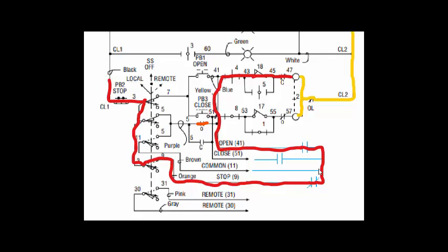that does is that brings voltage to this common wire to this contact on a selector switch, brings it over to the limit switch and torque switch to the coil as well. So that if this is a momentary push button or relay output that just gives us a pulse and it opens up, there's no voltage going this path but voltage can get to the coil via this path.